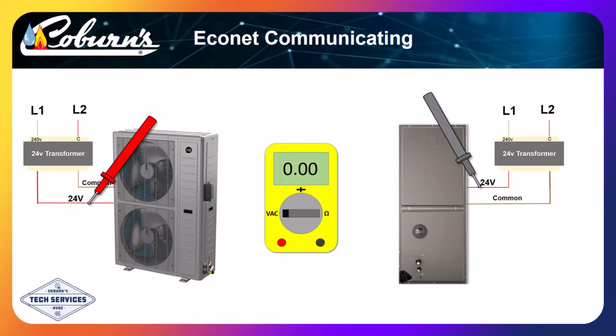We can verify the transformers are phased correctly with a meter. Again, we need to verify this before connecting our communication wires E1 and E2. Checking across the two 24-volt power wires should produce a very close to 0 reading on the meter. If the transformers are not phased correctly, the meter will read somewhere around 48 volts. This would indicate we need to swap the L1, L2 main power wires at the outdoor unit.